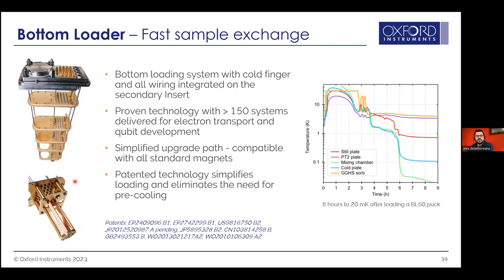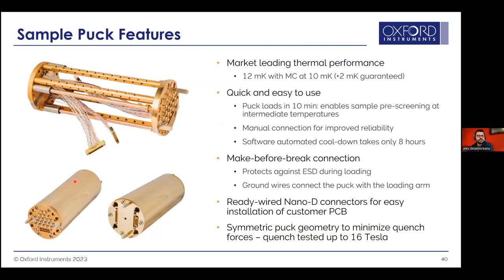You will have, in the bottom of the system, a sample puck. This is what we call our sample puck. This is where your sample will be installed. You can use copper grids with tapped holes to install any kind of sample holder.